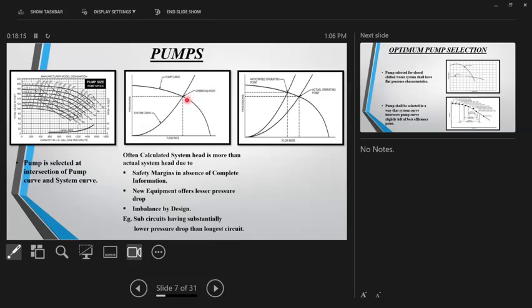So simple. Nothing great in this. You must have all seen this for long years. Now, this is all good in theory, that where the system curve intersects the pump curve, that's the operating point. It all looks good, but that's not how it happens in real-life systems.